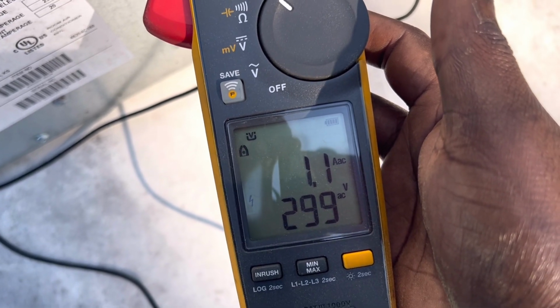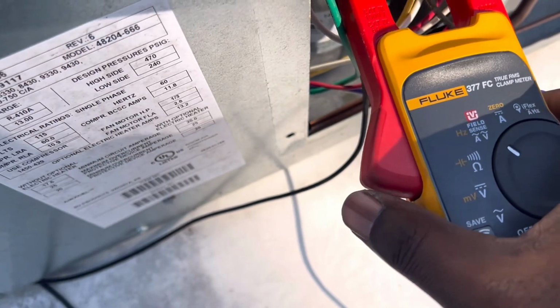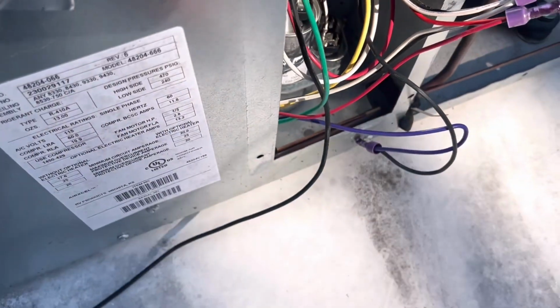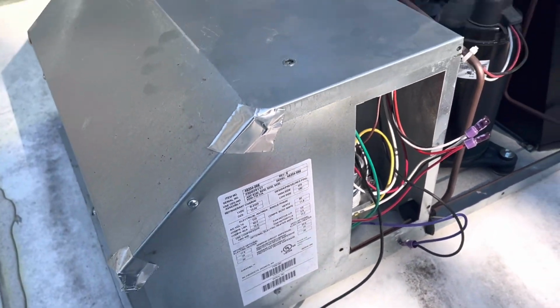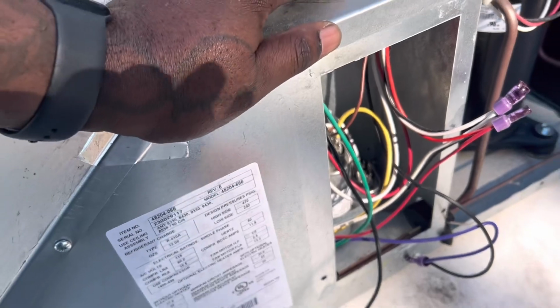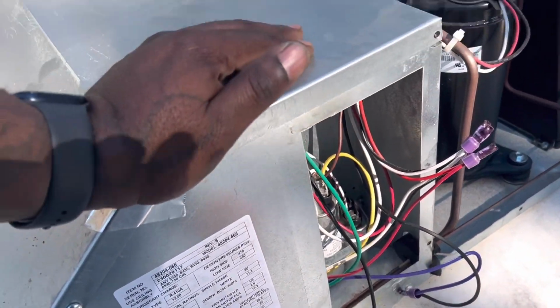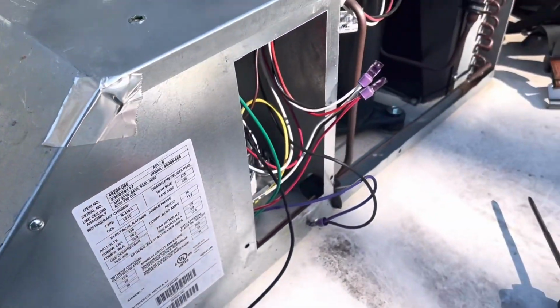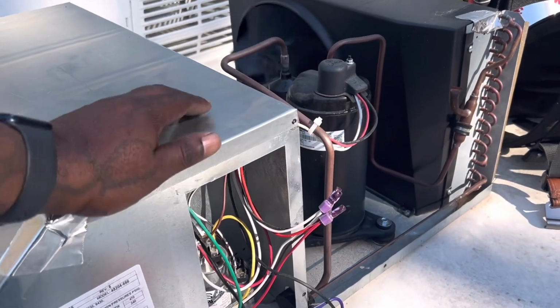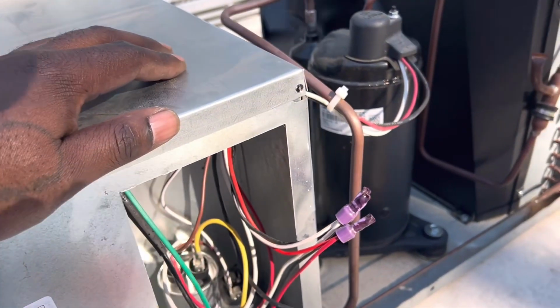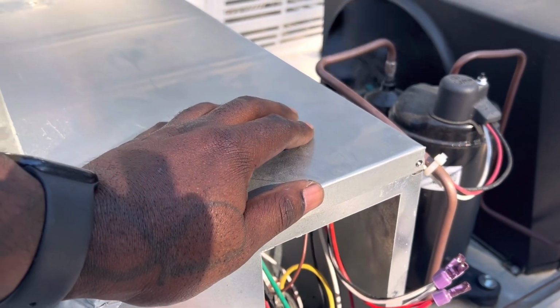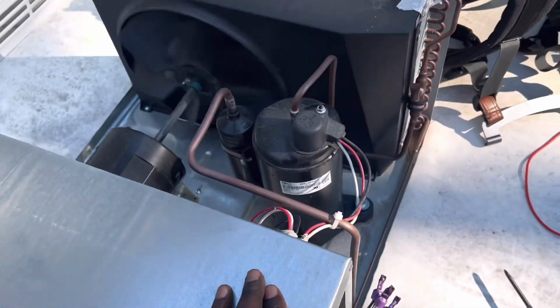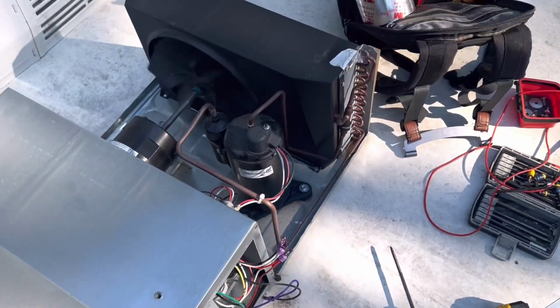Got my amp draw. So what that tells me is the relay in the control board is not sending the 110 out, and I need to check that, which is right in here, but you can get to it from the inside. But yeah, this one seems like a control issue. So I will check to see if I have my 12 volt input coming in, and then I will move on from there.